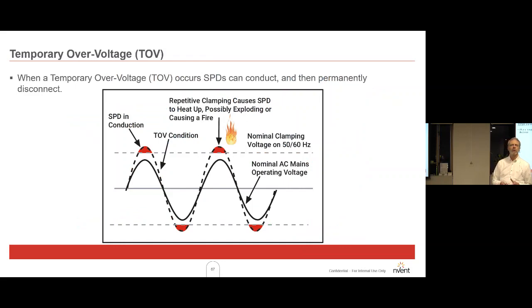What I will note is temporary overvoltage. If you're on a power supply where the supply voltage can rise higher than you would normally expect, so instead of being 230 volts, it's up to 270 volts briefly, that can burn out a surge diverter. That can happen at the end of a working day when industries drop all their loads before the transformers switch, so the supply voltage does jump right up. A standard surge diverter could burn out.